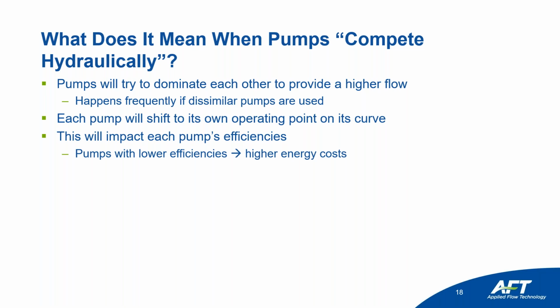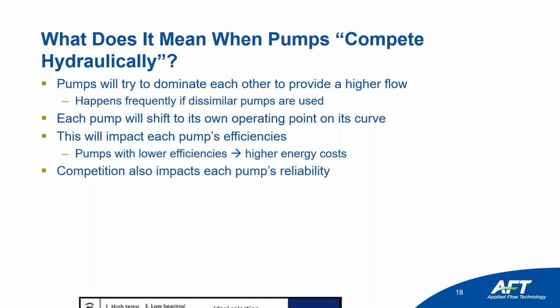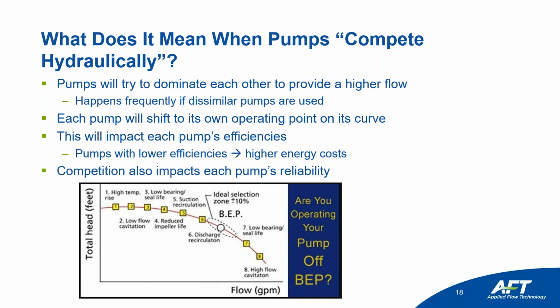Pumps with lower efficiencies lead to higher energy costs, but not only that, they operate further away from their best efficiency point. That's going to cause problems and going to lead to higher repair costs. And so again, that competition impacts your pump's reliability. So this is a graph of a pump curve that you could probably easily find with a Google search. And this identifies the problem areas on a pump curve.